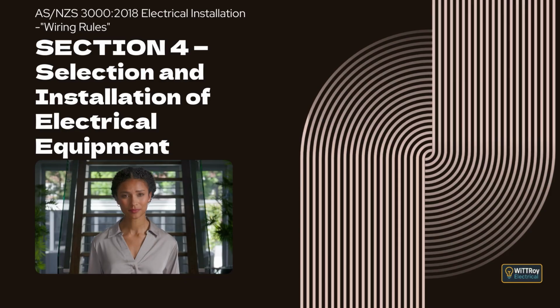Clause 4.4.2.1 Accessibility. This clause explains that socket outlets must be installed so that plugs can be easily inserted and withdrawn without damaging the plug or the flexible cord or cable. It explains that socket outlets must not be installed where a permanent fixture would restrict plug removal, and it also notes that where gas appliances are installed, the means of electrical isolation must remain accessible. Clause 4.4.2.2 Protection of socket outlets.